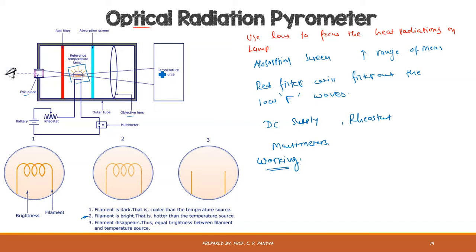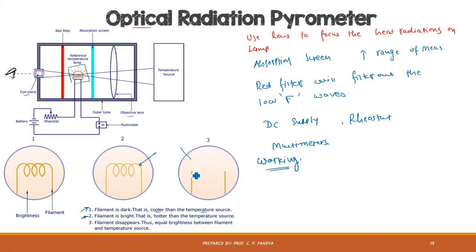If the temperature of the rays coming from the source is higher than the temperature of the lamp, you can see that the filament appears darker than the adjacent area — this satisfies the first condition where the filament is dark, meaning it is cooler than the temperature source. The operator will then adjust the rheostat so that the current through the filament is adjusted accordingly, until the temperature of the filament matches the temperature of the light coming from the source.